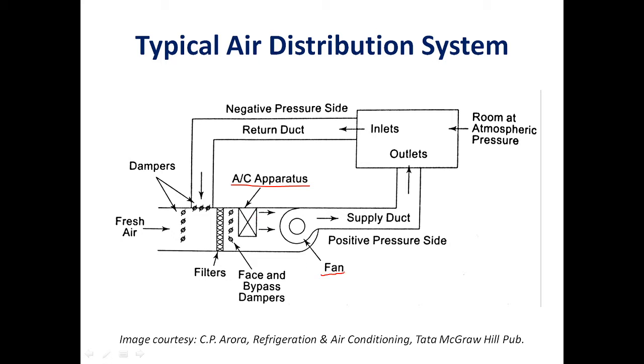The next component is the fan, which circulates air from the AC apparatus to the room. Different types of fans are used. The most commonly used is the centrifugal fan, also called a radial fan, preferred for its quiet and energy-efficient operation especially at high pressure. For very large air quantities in industrial applications, axial fans are also used.